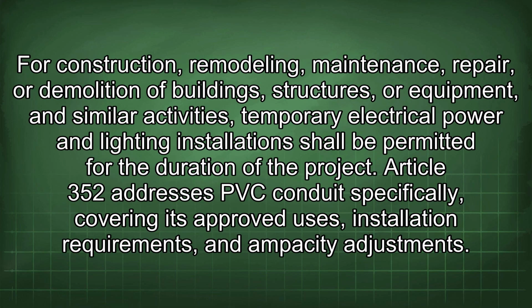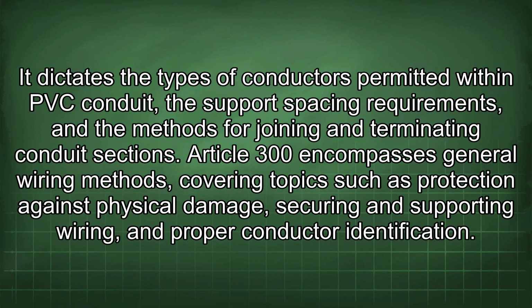For construction, remodeling, maintenance, repair, or demolition of buildings, structures, or equipment, and similar activities, temporary electrical power and lighting installation shall be permitted for the duration of the project. Article 352 addresses PVC conduit specifically, covering its approved uses, installation requirements, and ampacity adjustments. It dictates the types of conductors permitted within PVC conduit, the support spacing requirements, and the methods for joining and terminating conduit sections. Article 300 encompasses general wiring methods, covering topics such as protection against physical damage, securing and supporting wiring, and proper conductor identification.